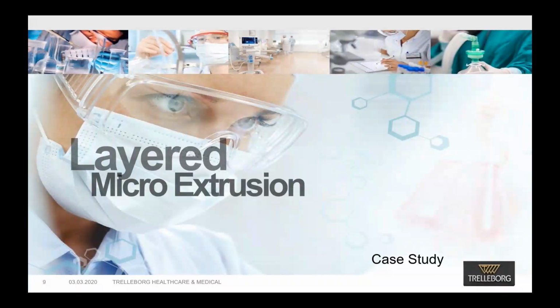So that brings us to our first case study, which is the development of a layered silicone micro extrusion. That's a mouthful. To give you some background, a layered extrusion refers to a specific type of multi-component extrusion. These can be as simple as, let's say, two co-extruded silicones consisting of a standard medical silicone, which is then combined with a radiopaque stripe, that stripe being used to locate it in an X-ray or a fluoroscope. Additional complexity can include embedding this stripe, which may be compounded with barium, which gives it the radiopacity, within a second silicone that has no additional compounding. This might be done to minimize risk associated with the additive in contact with the most sensitive human anatomy, such as with a hydrocephalus shunt implanted in the brain, to prevent the stripe material from contacting the brain.